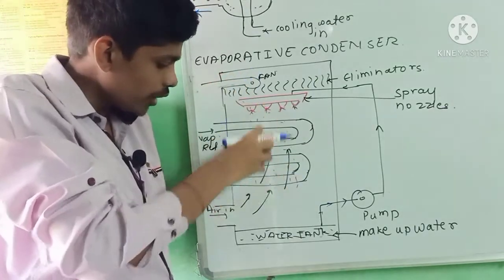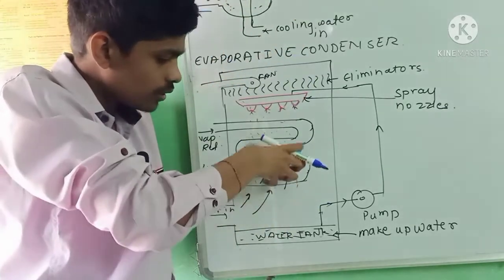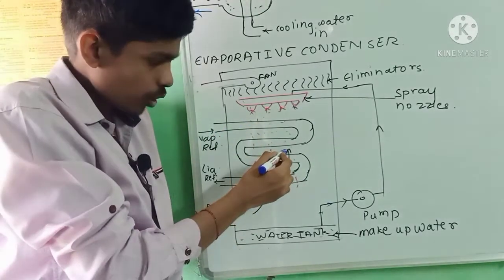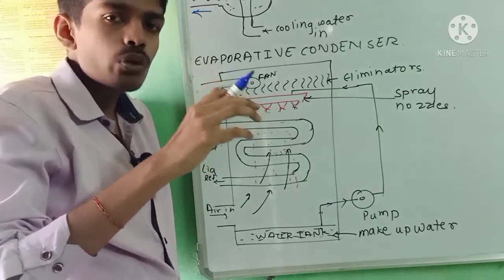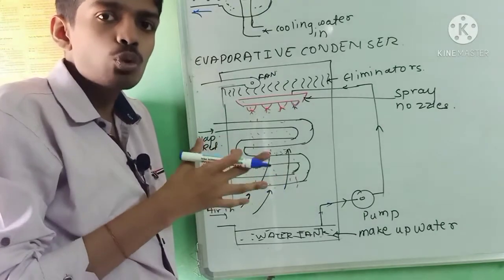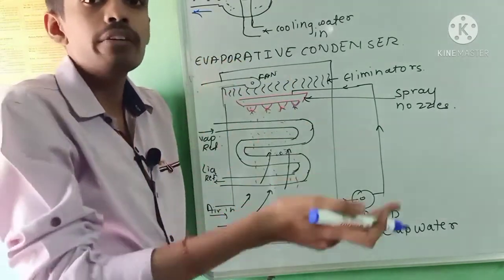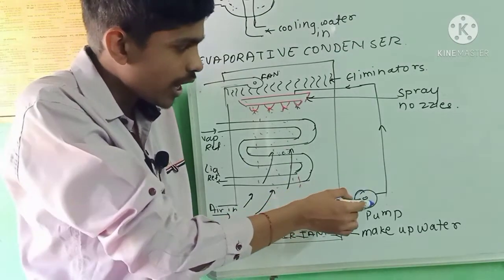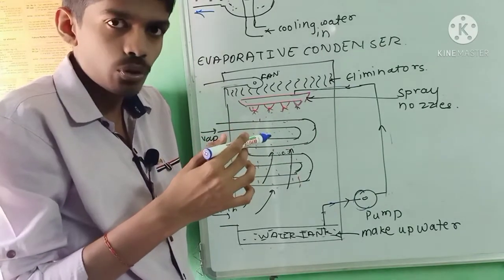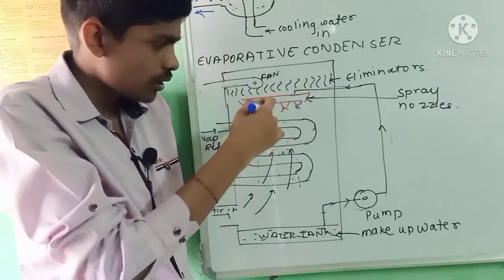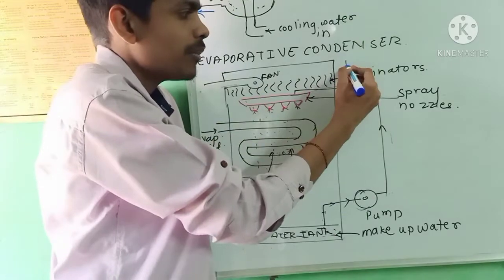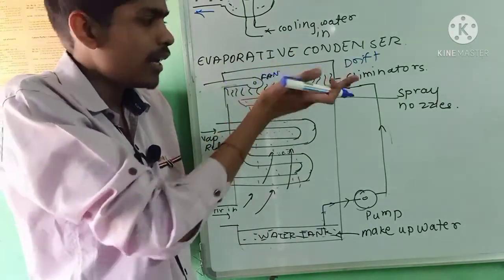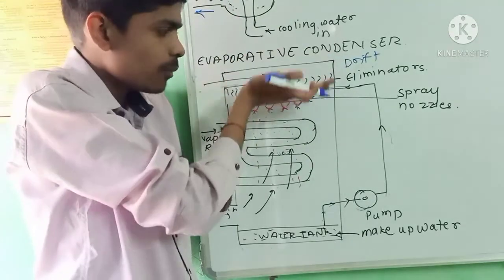The fan draws air from the bottom side towards the top of the condenser. As this air passes over the coil surface, water particles on the surface also evaporate, aiding cooling. Most of the conversion of vapor refrigerant into liquid refrigerant is achieved by this evaporation. The cooled water collects in the water tank at the bottom and is recirculated by the pump to the spray nozzles — this is the recirculated water system. Drift eliminators prevent water particles from escaping with the air; any captured water particles fall back into the tank.